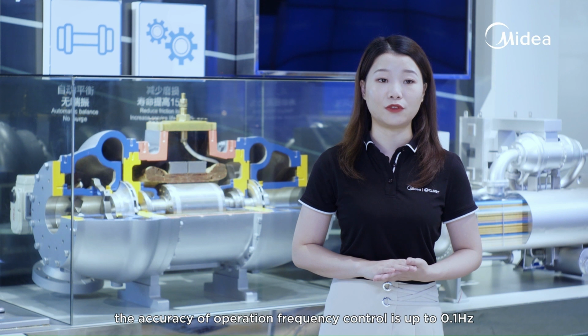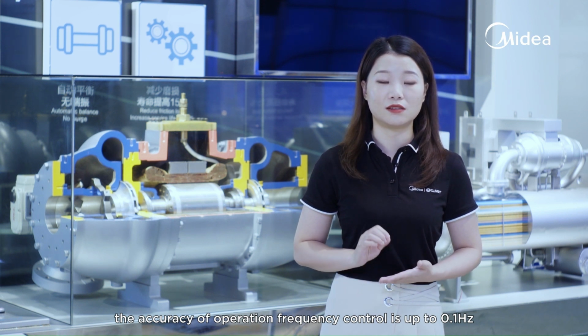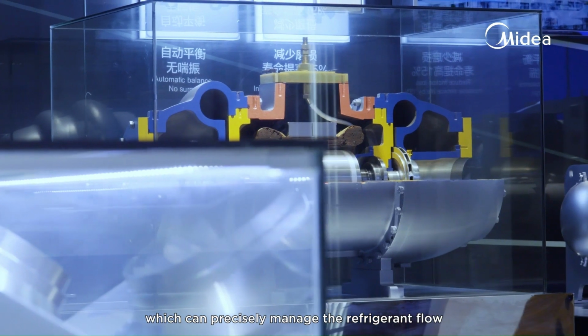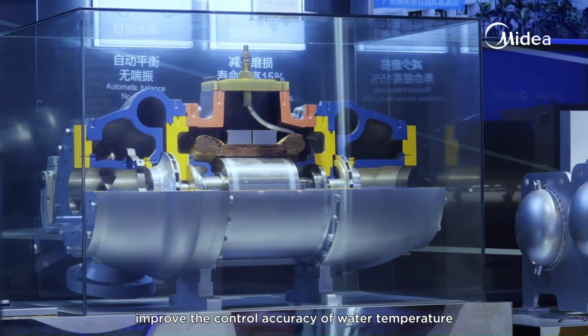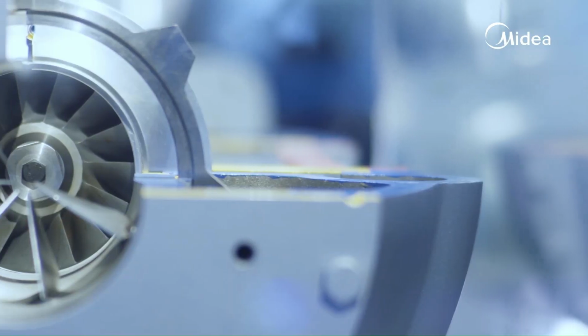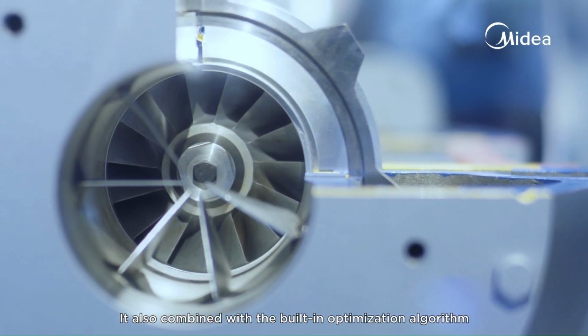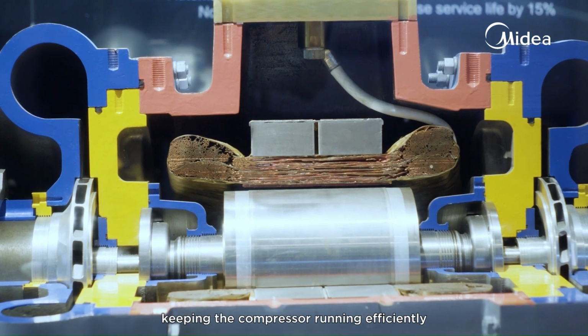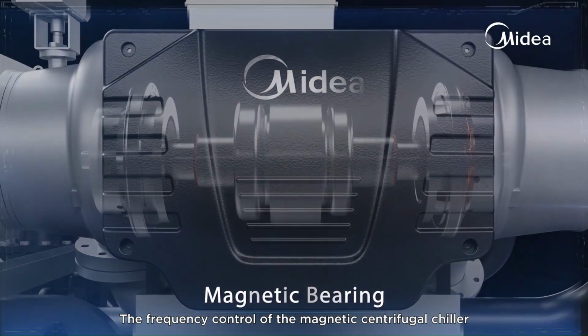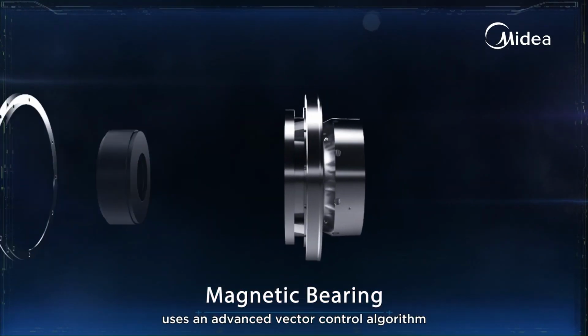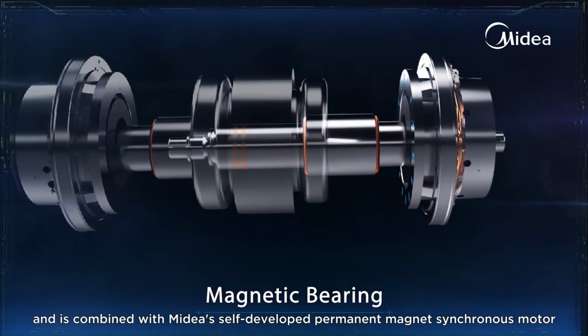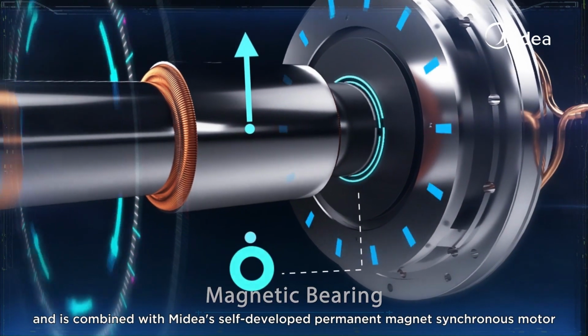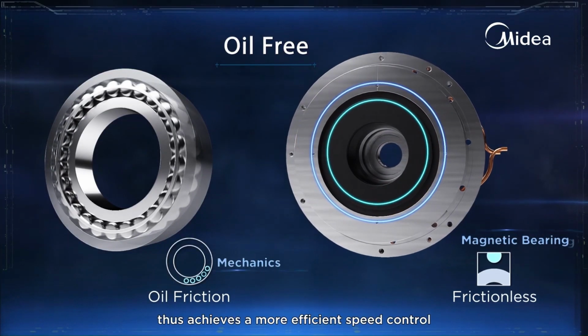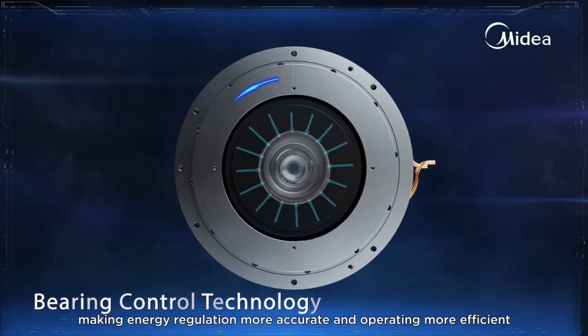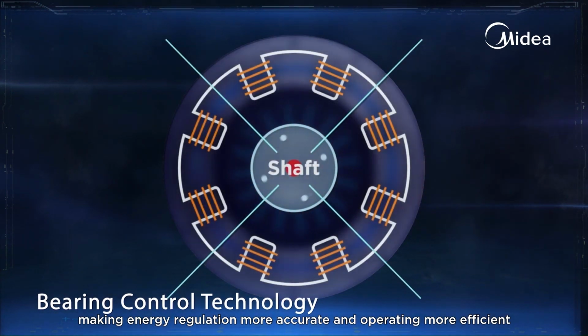Meanwhile, the accuracy of the operation frequency control is up to 0.1 Hz, which can precisely manage the refrigerant flow and improve the control accuracy of water temperature. It also combined with the built-in optimization algorithm, keeping the compressor running efficiently. The frequency control of the magnetic centrifugal chiller uses an advanced vector control algorithm and is combined with MIDEA's self-developed permanent magnet synchronous motor. Thus achieves a more efficient speed control, making energy regulation more accurate and operating more efficient.